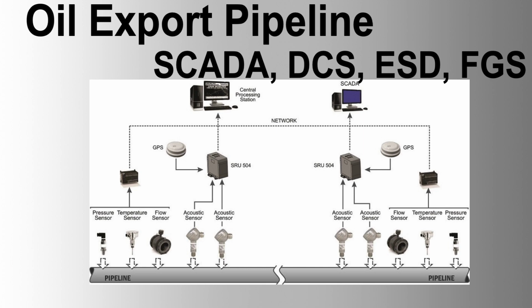Master Control Room, MCR, located at the primary pumping station with a backup at the oil receiving terminal. Communication: dedicated fiber optic backbone with redundancy through leased circuits and radio communication. Servers: dual redundant SCADA servers in a hot standby configuration to ensure high availability. Data acquisition: interfaces with field devices, tank farm management systems, and metering skids to acquire data. Displays: graphical displays, alarms, real-time and historical trends, and reports for operator interface.